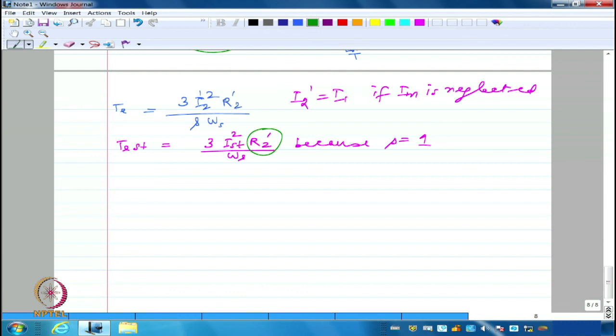I'll bring down the starting current, but unlike the reduction in starting torque that I got in squirrel cage, where I had to tamper only from the stator side and couldn't touch the rotor side at all, here I will be able to touch and modify the rotor resistance. So I would be able to get a good amount of starting torque as compared to squirrel cage.